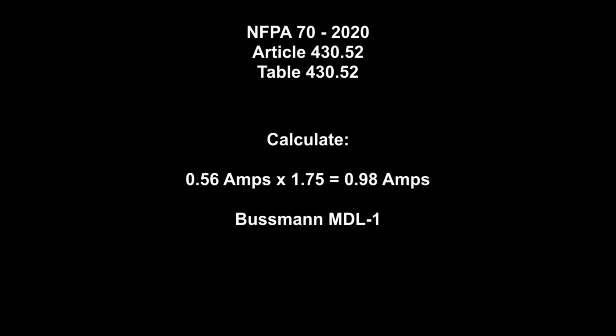Okay, if I'm following NEC section 430.52, rating or setting for individual motor circuits, and table 430.52, the circuit time delay fuse ampacity for a single phase motor can be no more than 175% of the motor's full load current. So my high-speed current of 0.56 amps times 175% is 0.98 amps. However, if that calculated value doesn't correspond with a standard fuse size, there's an exception that permits using the next higher standard size fuse. I was planning on using a 1 amp slow blow fuse anyway, so my Bussmann MDL1 fuse selection works out fine. And my relay contacts will be very well protected.